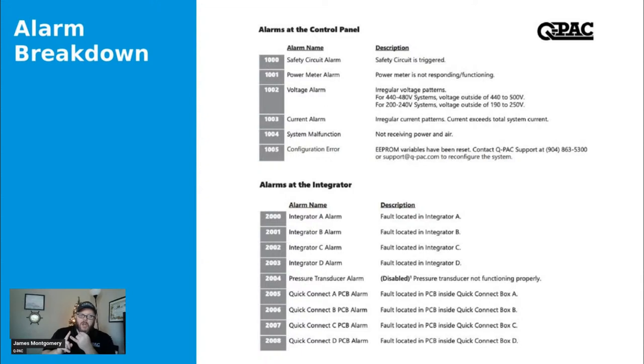So I'm not saying you should operate outside of the 5% above or below the rated voltage, but it won't shut the unit down. This is more like an, oh, by the way, used for later to say, hey, why did we have problems? Well, your voltage was always under or over. These are notifications for you, the user, and the owner of the system to know that they've got a parameter. Maybe your building runs higher or lower voltage, but it's still within the 5% required, then you won't get this alarm. This alarm will only go off when it's outside of that 5%.